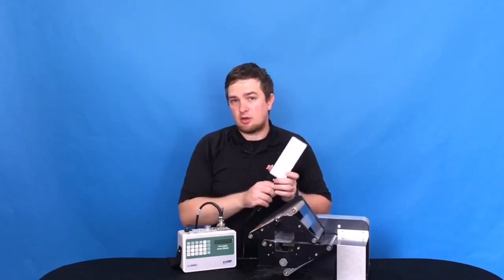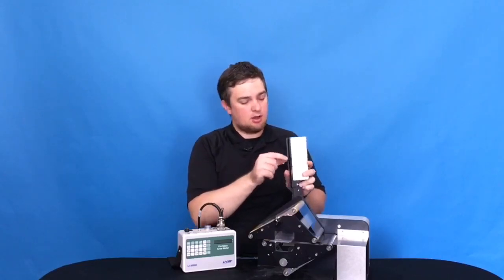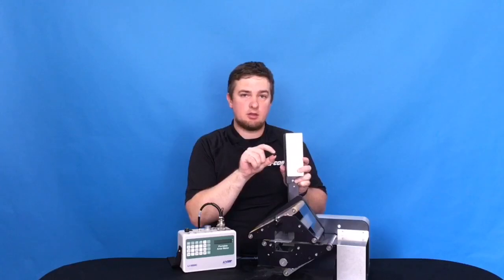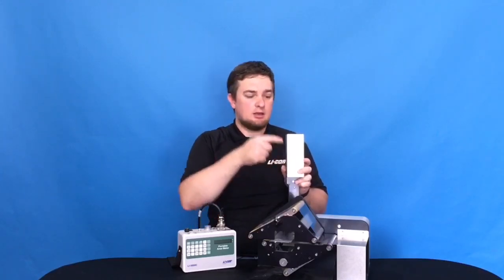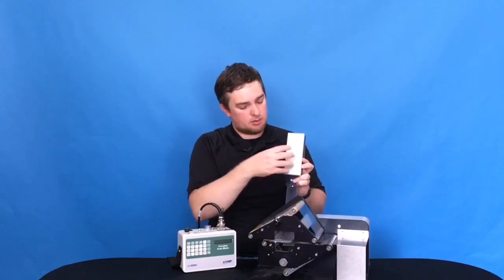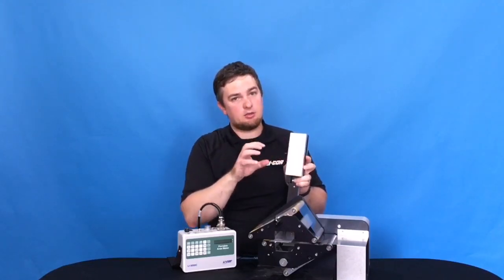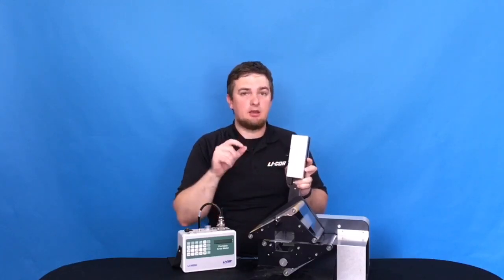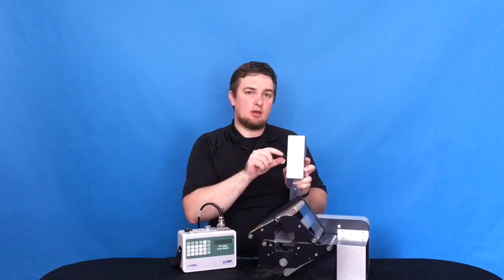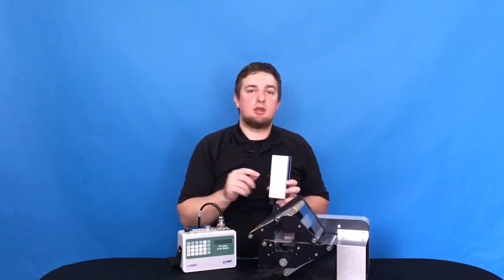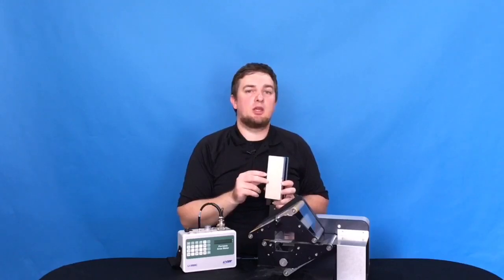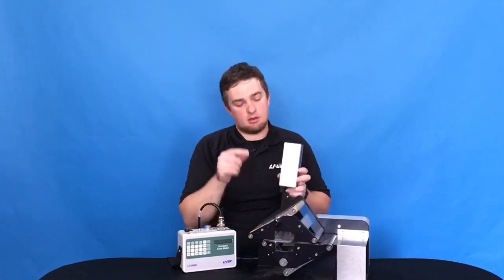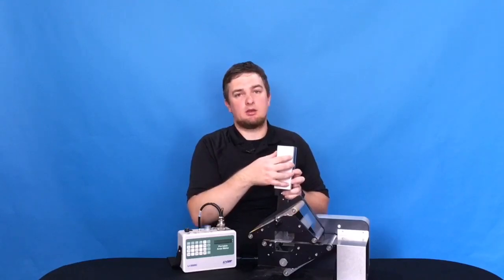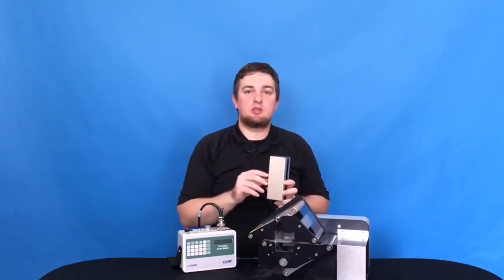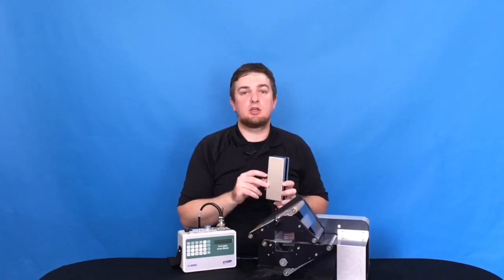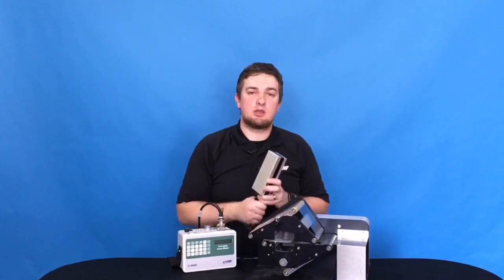There is also a dust trap inside the sensor head. So it basically goes around the length encoding cord, but on the inside. If you were to remove these screws from the top half of the sensor head and then gently peel that off, you would see a small red filter that goes around this cord. You may need to pop it out of place and clean that out. You may need to replace it, but generally you can just clean the dust and dirt off of that, pop it back into place, and put the sensor head cover back on. That may need to be checked more frequently if you have a lot of pollen or dust or dirt, and maybe less frequently if you don't use this as much.